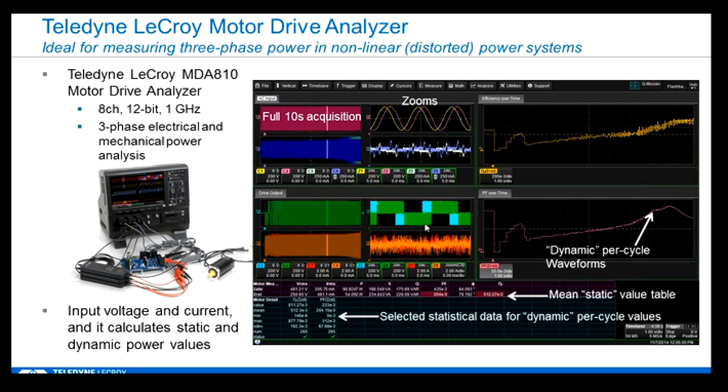And this is the drive output here. This is a voltage envelope right here for the two lines I'm measuring. And then this here is the current. It looks pretty noisy. It is. It's drawing a relatively small load. There is a lot of noise pickup just in the environment from all the switching activity. But that is the current right there. You can kind of see the sine wave being delivered like that.